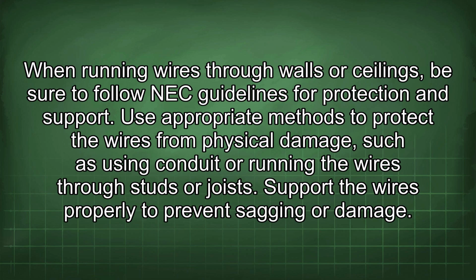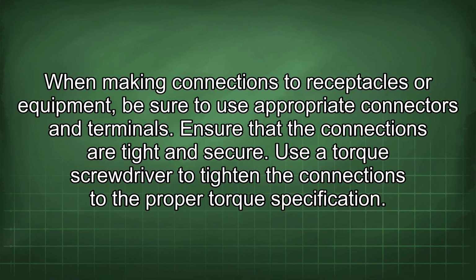Support the wires properly to prevent sagging or damage. When making connections to receptacles or equipment, be sure to use appropriate connectors and terminals. Ensure that the connections are tight and secure. Use a torque screwdriver to tighten the connections to the proper torque specification.